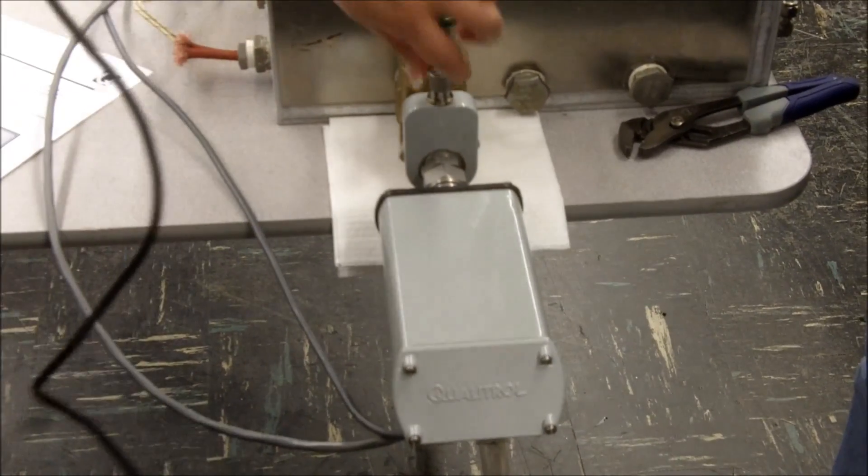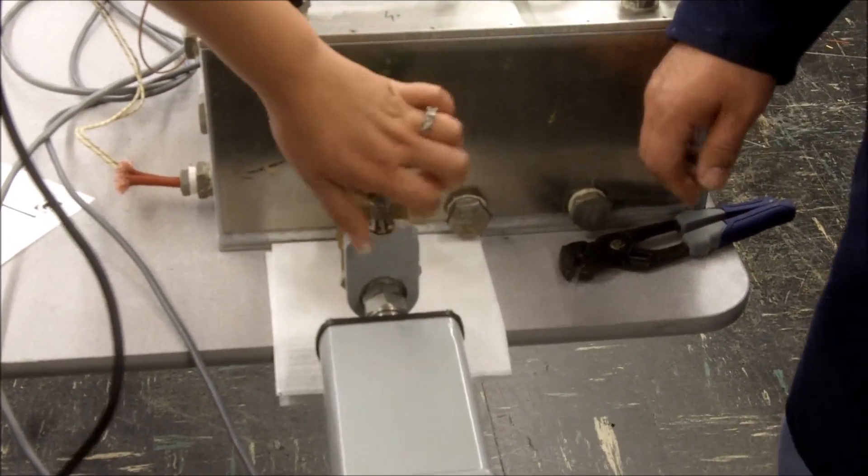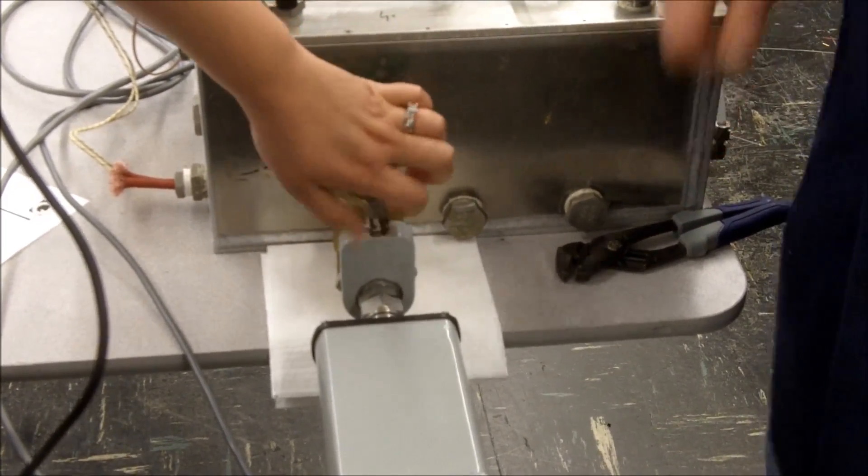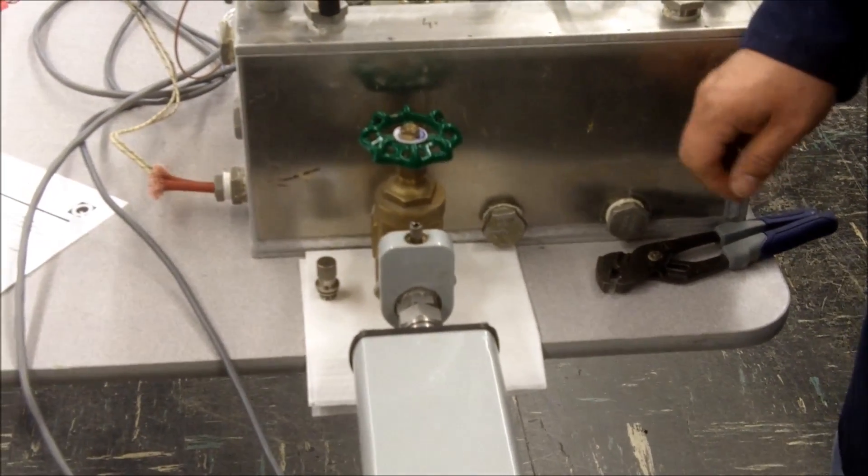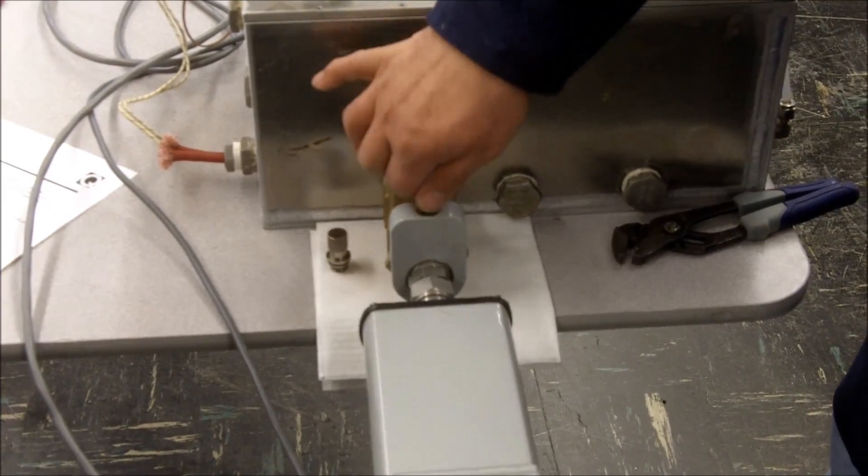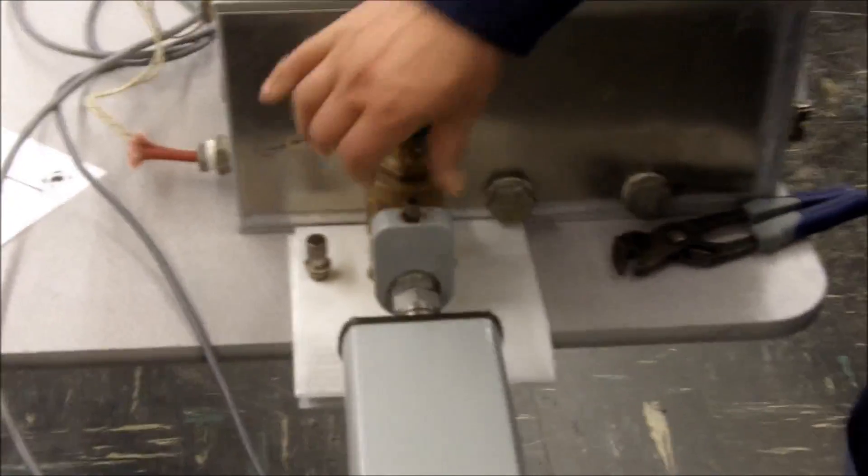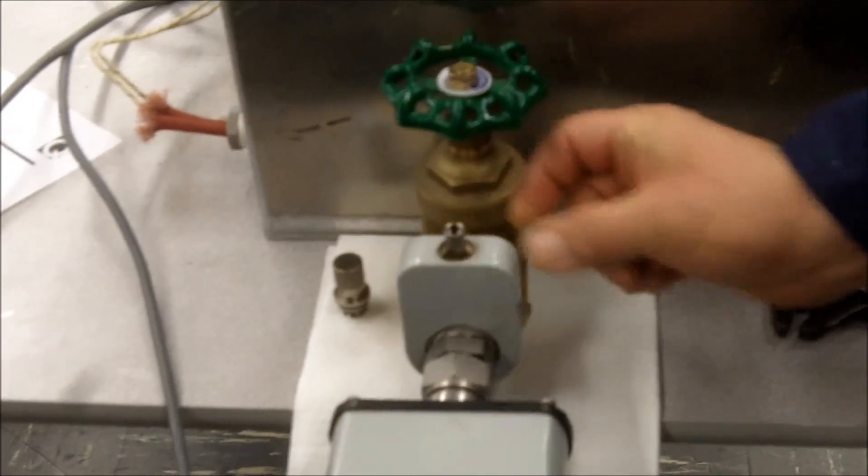So the first step would be to open your sampling port here, your sampling valve for the DGA 150. You want to turn the sampling valve in order to let oil flow freely to remove any debris or water that may have collected to make sure that you have that bulk uniform sample.